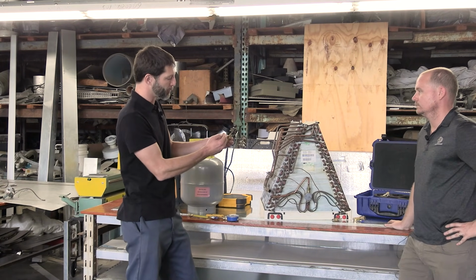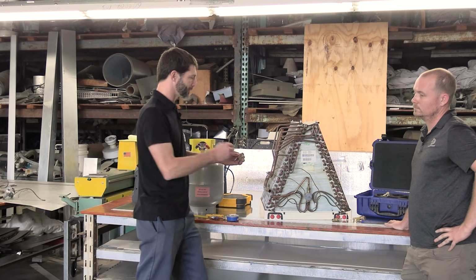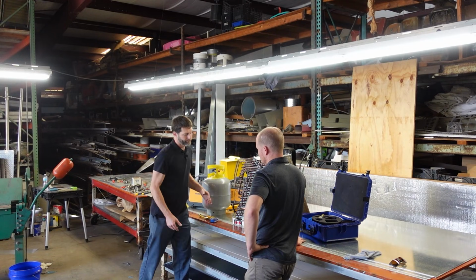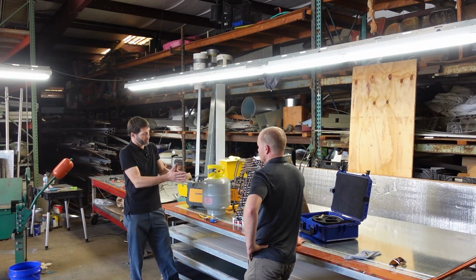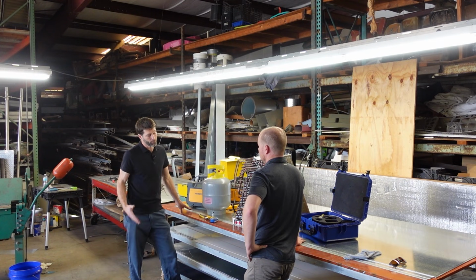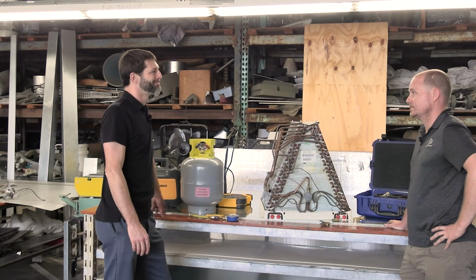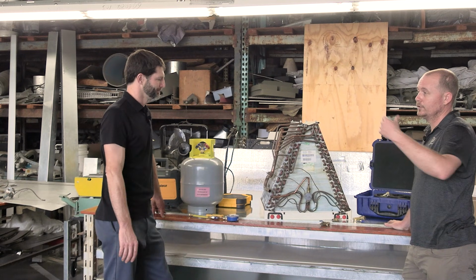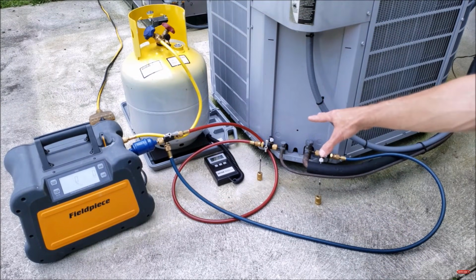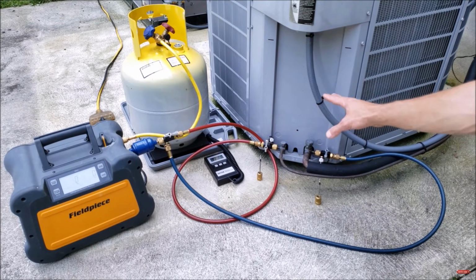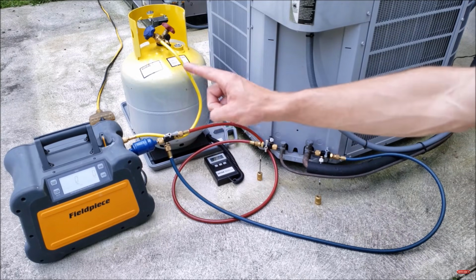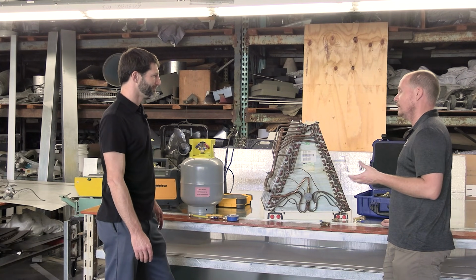At least you're getting the valve core out of the way to try to get the restrictions out so you can recover your refrigerant quickly. Yeah, and so pull from both sides whenever possible. Hook one hose to your liquid line, hook one hose to your suction line. Again, typical split system type of setup. You can tee those together if you want right before you go into the tank. Again, using larger hoses helps.